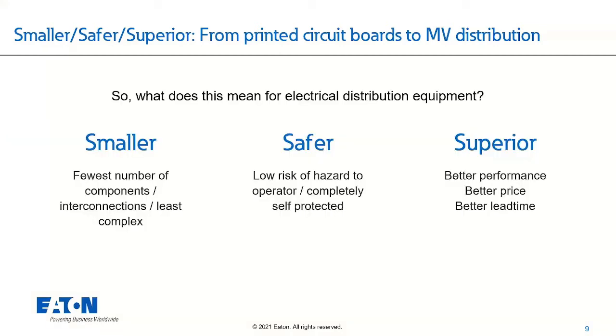So ultimately, what does this mean for electrical distribution equipment in the MV and LV world? This is where I derive my smaller, safer, superior commentary. Smaller is really about eliminating unnecessary redundancy, and I'm not referring to a double-ended substation type of redundancy - that's more of an obvious backup scenario. I mean things like multiple current sensors or multiple voltage sensors, where you have overlapping zones of protection, and you want that to be as seamless and easily coordinated as possible.